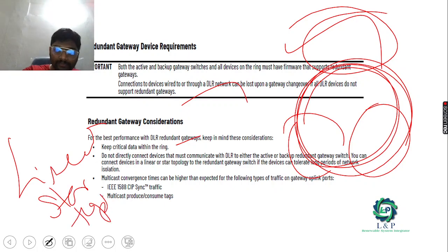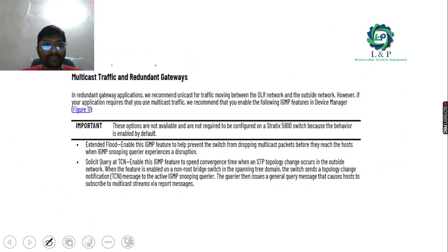Connect to the redundancy gateways if the device can tolerate a long period of network isolation. And most importantly, the multicast convergence time can be higher than expected for the following types of traffic which occur in the uplink ports: IEC 61588 CIP Sync traffic or the multicast produce or consume tags.